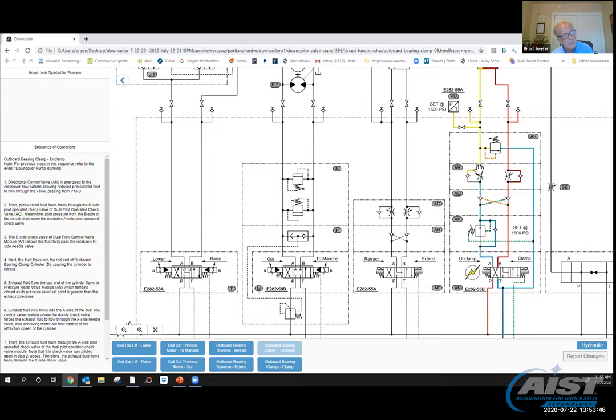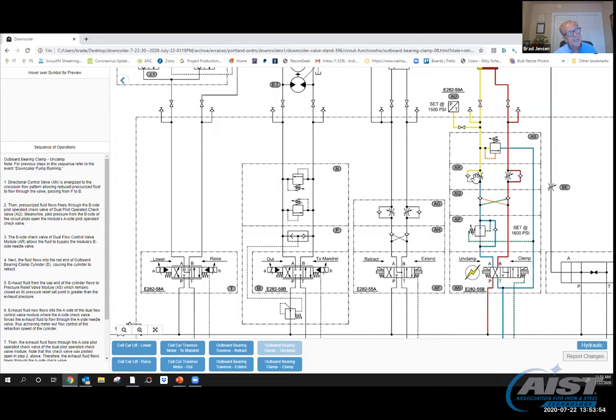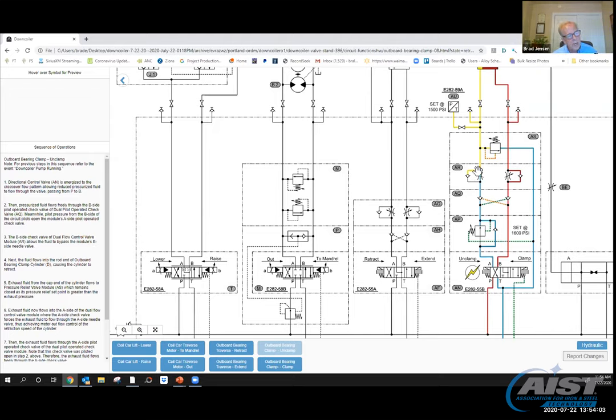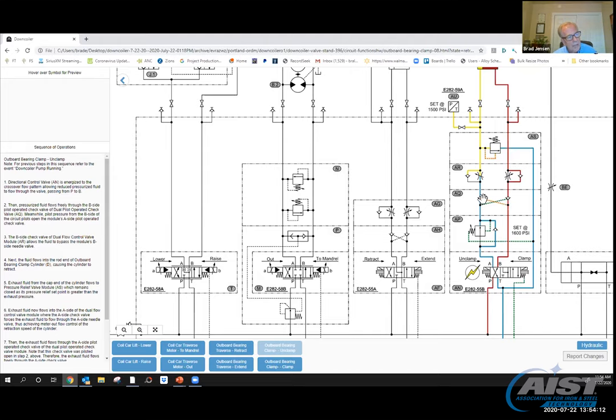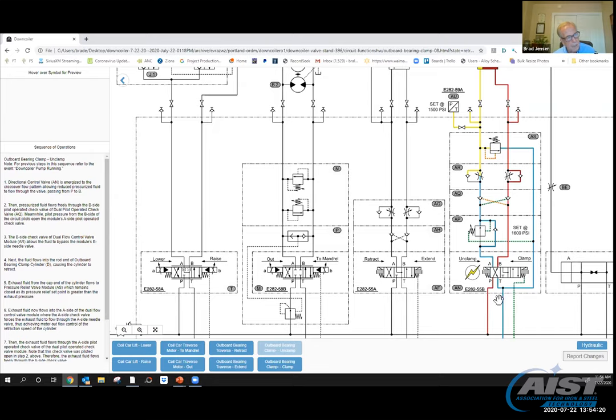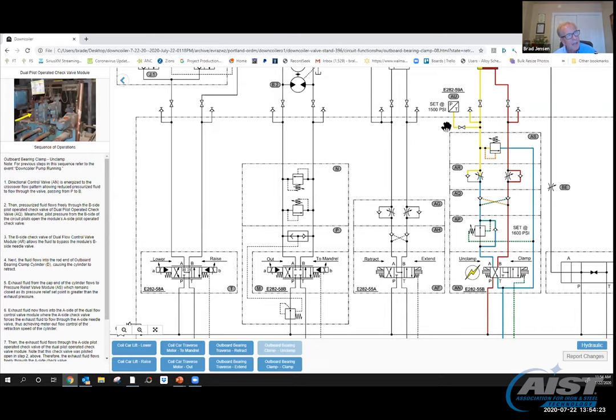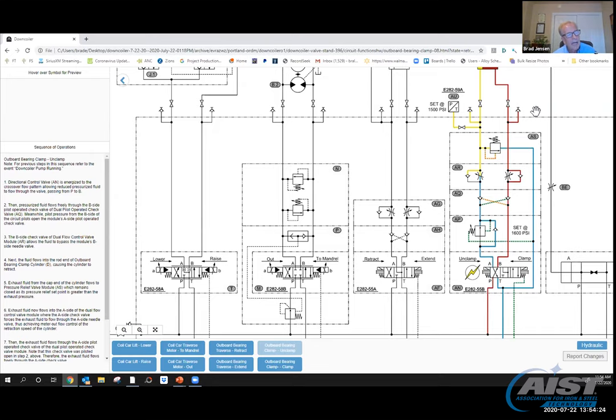The other components I have stacked here—I've got a pressure reducing valve. You can always tell a pressure reducing valve by the nose that hangs out. It's a pressure valve, but what it does is it actually reduces something below compensator setting on the pump. We don't want 2200 PSI ever based on what it's pushing against on this cylinder up here. So I have to put a reducing valve on the A side. And then I want to slow it down. Here's this yellow flow here. Here's a flow control valve—here's a check that shows reverse flow around it. By the way, I'm coming up the wrong side here. I'm free-flowing around it here. I'm coming back here. So I'm metering out, not in. For various reasons, that's important to know too.